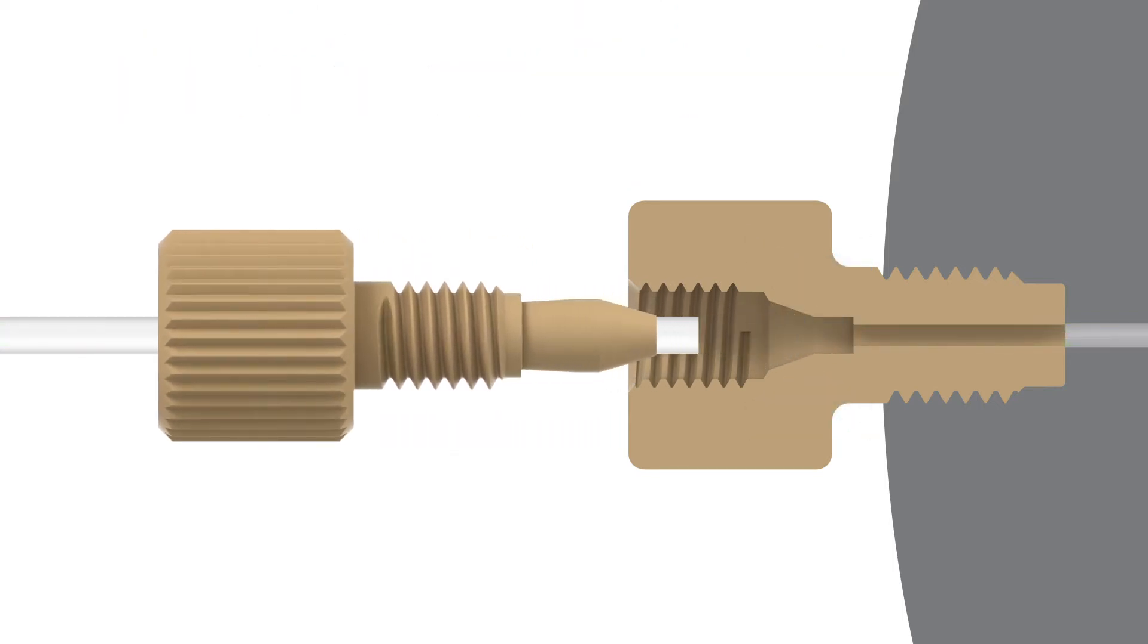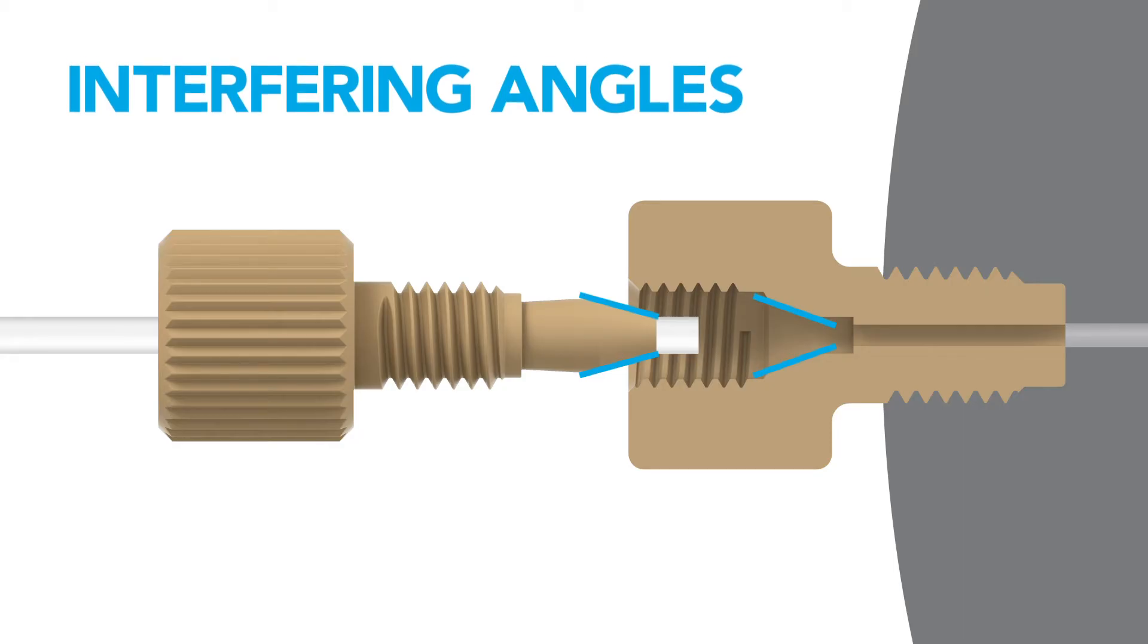This compression is driven by a concept called interfering angles. The primary tapered portion of the ferrule will face the tapered portion of the receiving port.